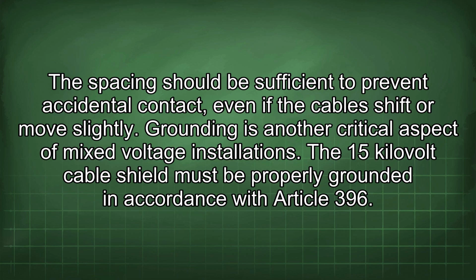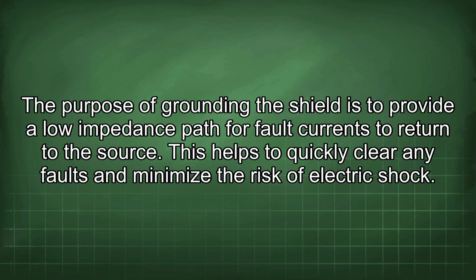Grounding is another critical aspect of mixed voltage installations. 15 kV cable shield must be properly grounded in accordance with Article 396. The purpose of grounding the shield is to provide a low impedance path for fault currents to return to the source. This helps to quickly clear any faults and minimize the risk of electric shock.